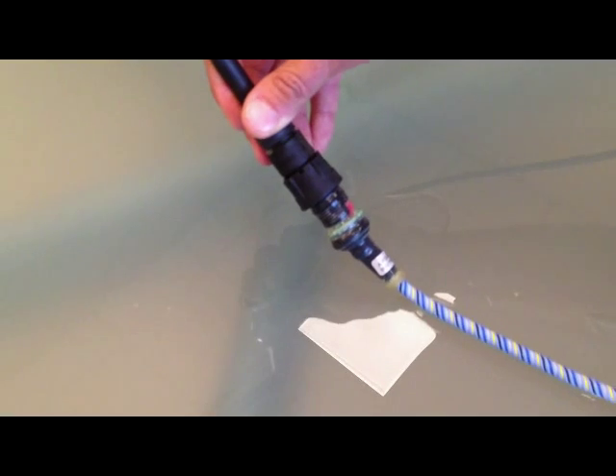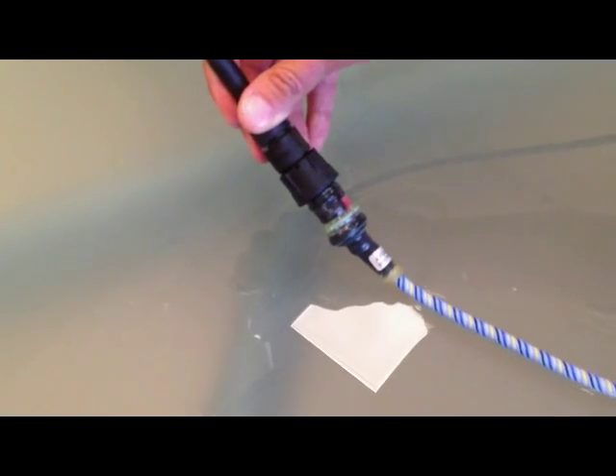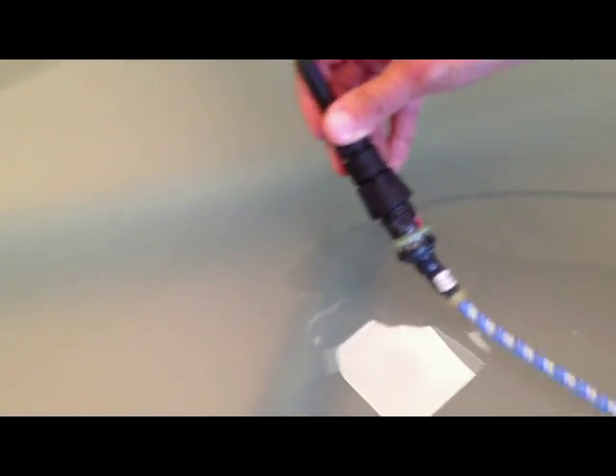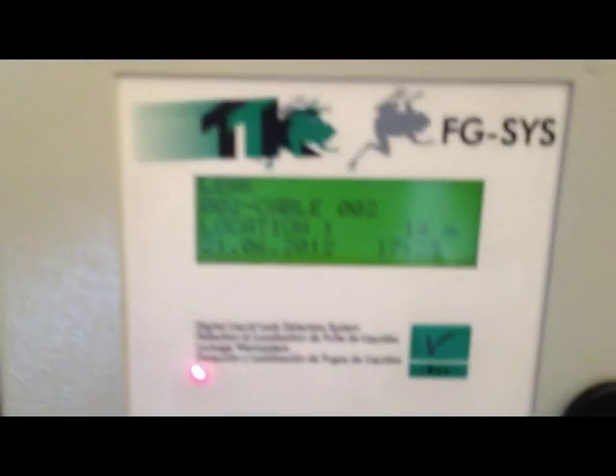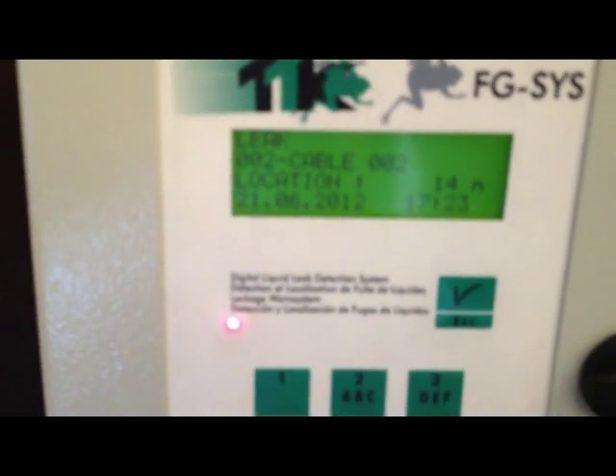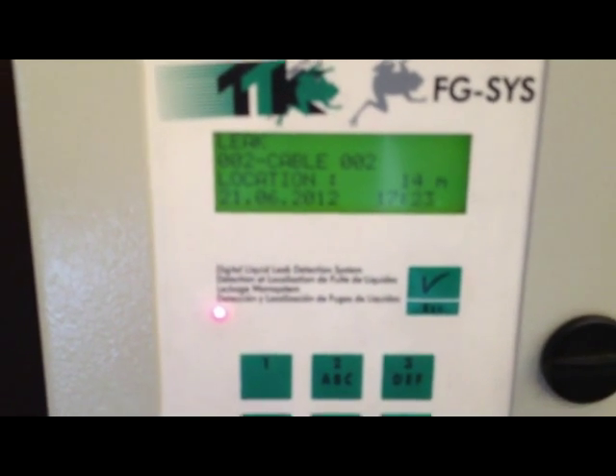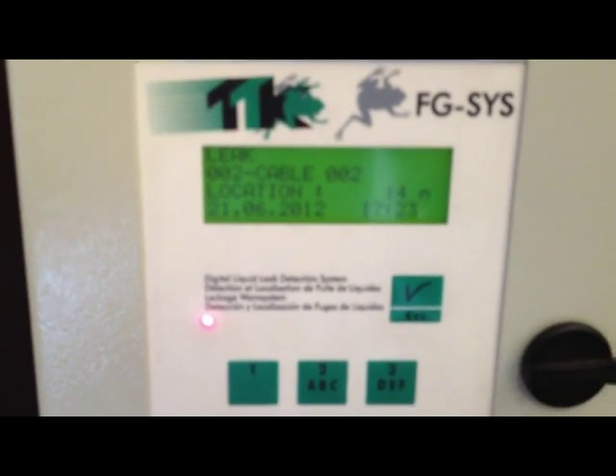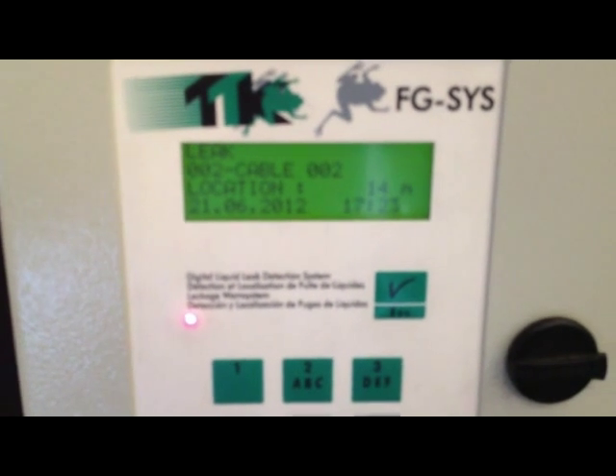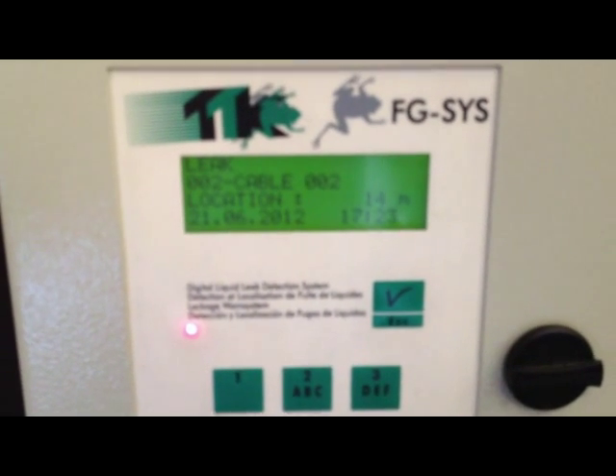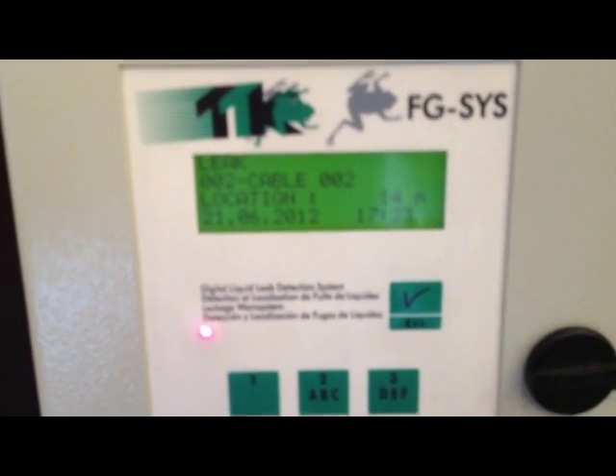So it moves green to red, and we check the sounds again. And we can read cable number two, location of the leak, 14 meters, plus or minus one meter.